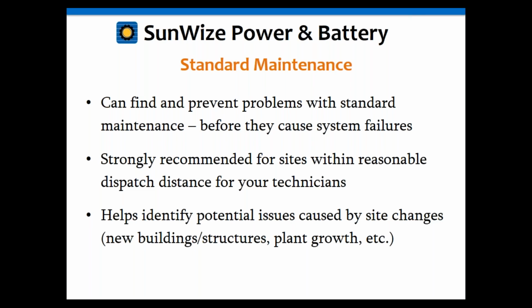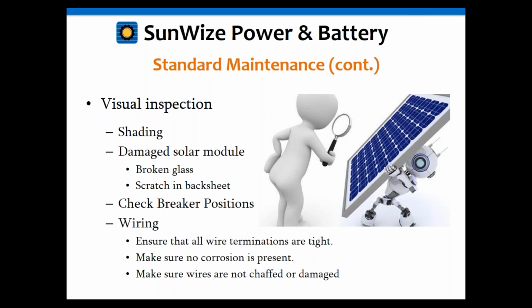And again, we're going to get into some more detail on the things you can look for, such as any issues with wiring and even problems with vegetation growth at the sites. So we're going to start with the visual inspection, where you're going to be looking for shading from the solar array. A lot of times you're going to have vegetation that has grown up that wasn't there before. Stuff can grow very quickly. So you may have installed the system and it worked great for a couple of years, and all of a sudden it's not working because a tree has grown up in front of it, or some other type of vegetation, a bush or grasses have grown too high or whatever. So it's important to look for that.